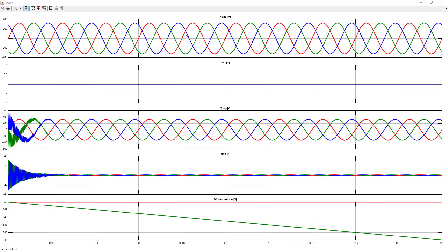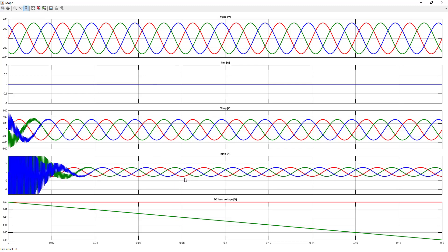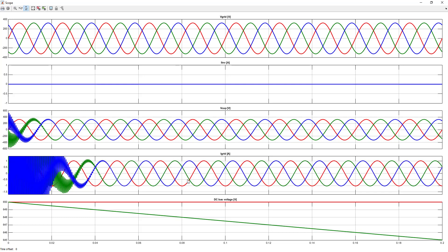The result should look like this. What you see here is the grid voltage - you see the three phases shifted by 120 degrees. As predicted, the inverter current is zero. This is the voltage at the capacitor of the LCL filter. Here we have the grid current. We can zoom in. We see that it's indeed a current, and it's around 1 amp. What you can do as an exercise is compute and verify that indeed this current must be around 1 amp with the values of the LCL filter I've given you.